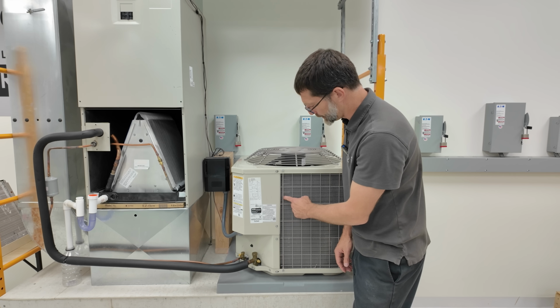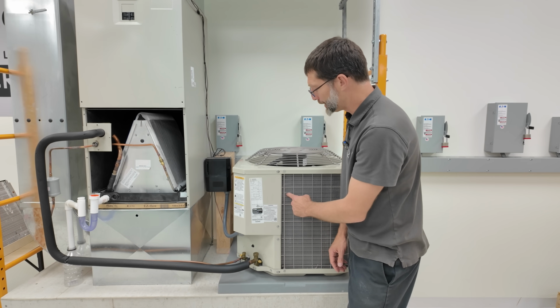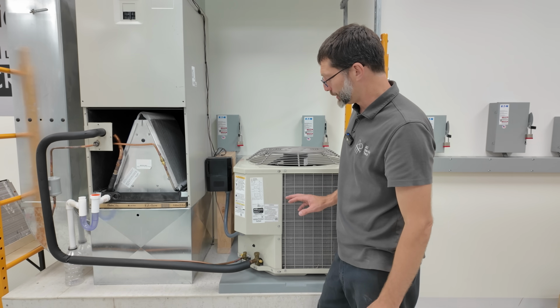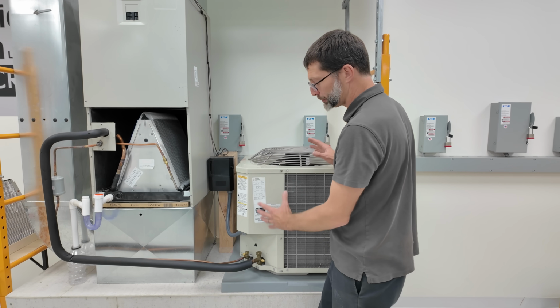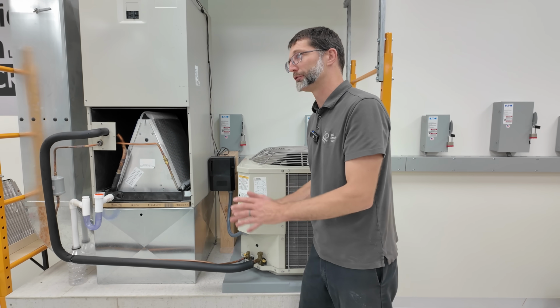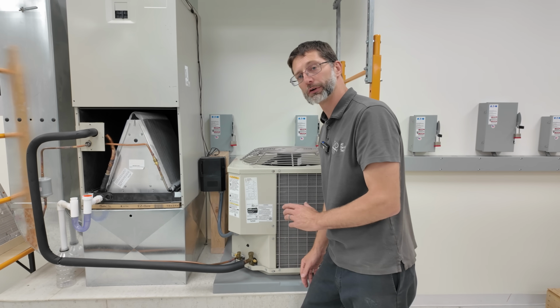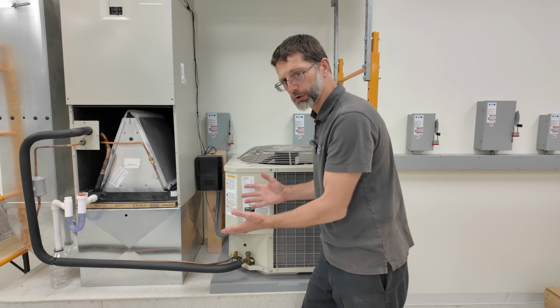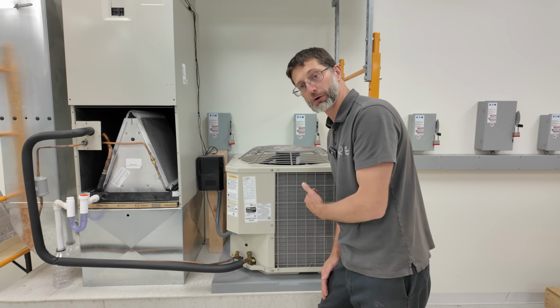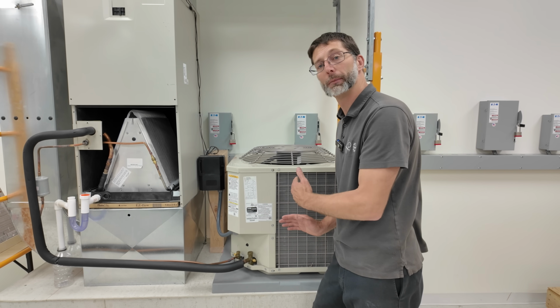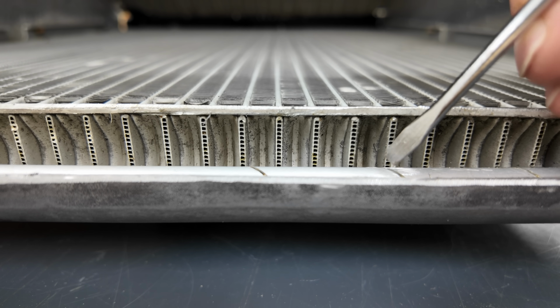Now this one right here is a conventional copper tube and aluminum fin. And so these will hold up, and you can pump a system down like this potentially, say if it has a reciprocating compressor or something like that. But if it has a scroll compressor, you don't want to pump it down all the way anyway. But if it's a microchannel coil, you definitely can't pump it down because you have those tiny little pathways in the tubing of the microchannel coil.